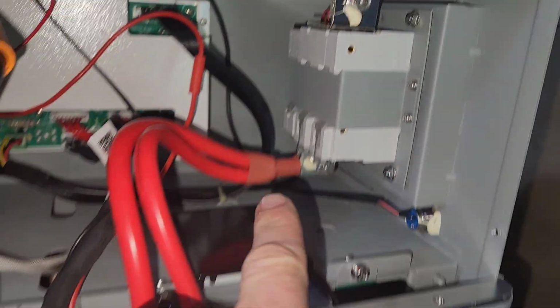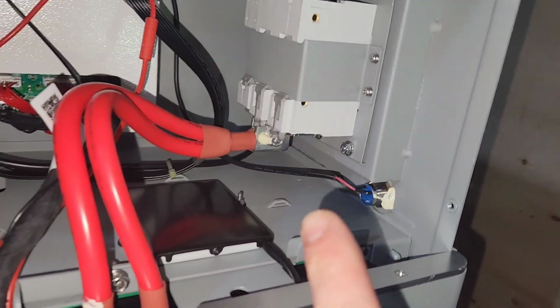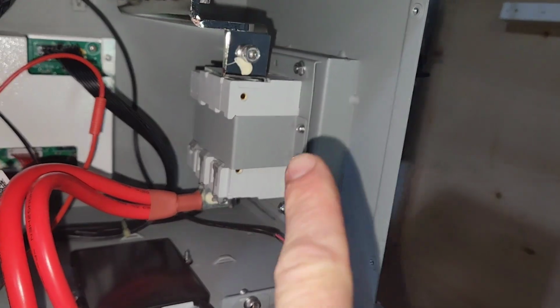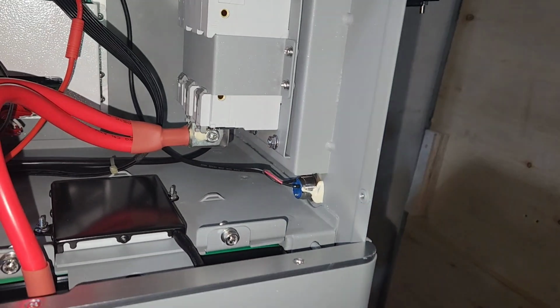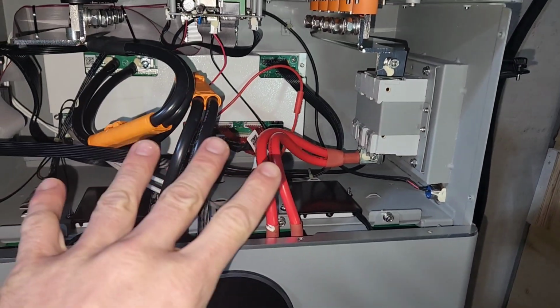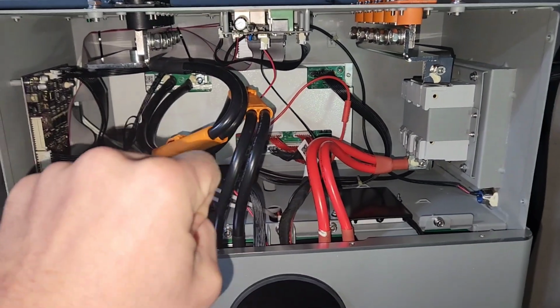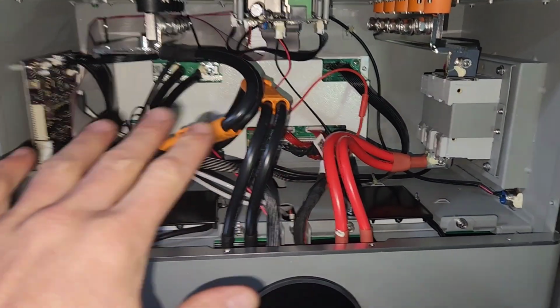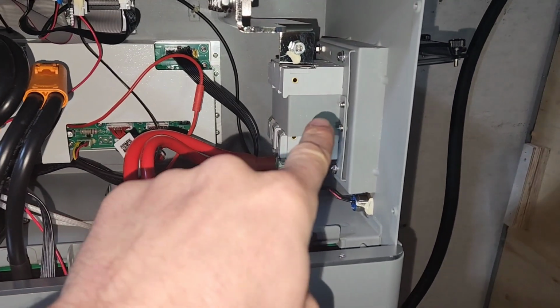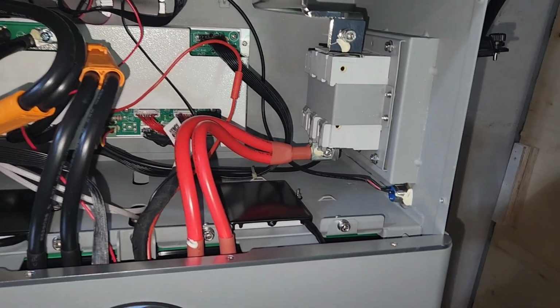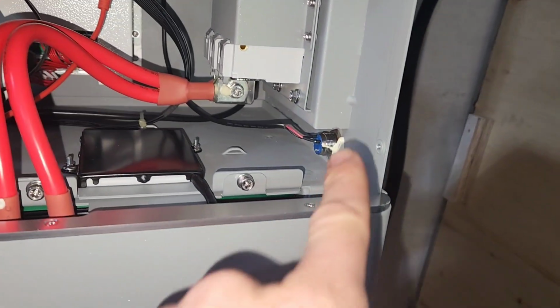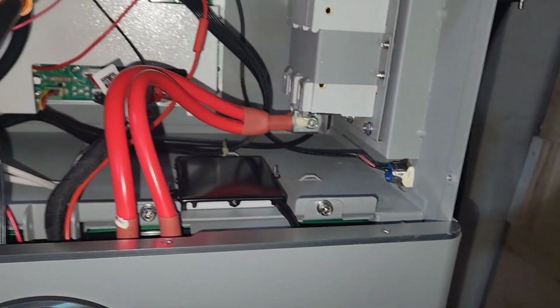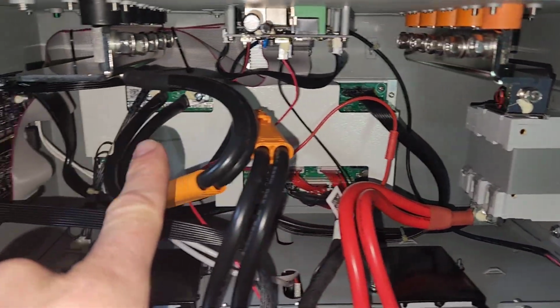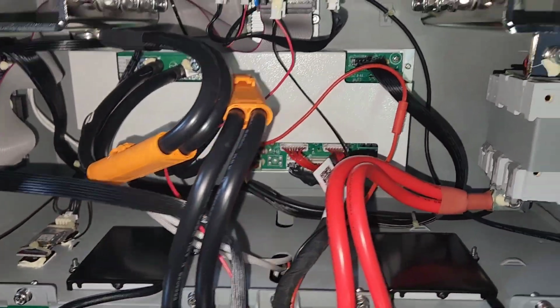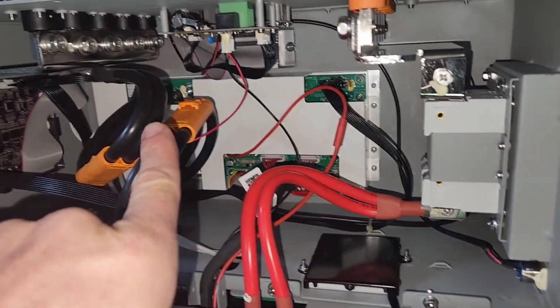So the positive comes out here, goes through that breaker. So if you have too much current flowing out of the battery, the BMS will shut everything off first. If for some reason the BMS fails, you have the mechanical breaker here that should also add extra protection. There's the on-off switch right here. And that back box, looks like that is the BMS right there.